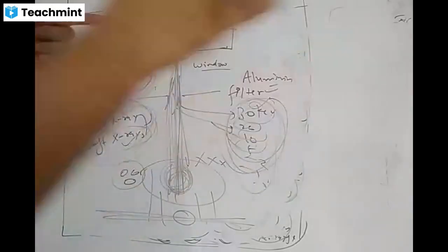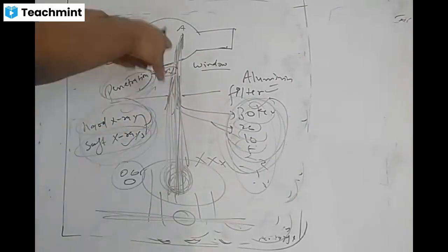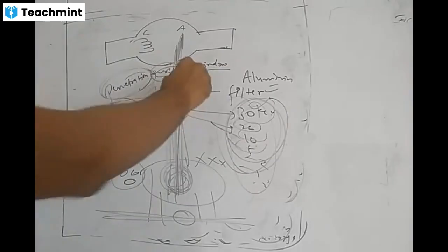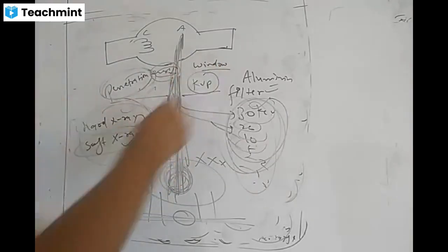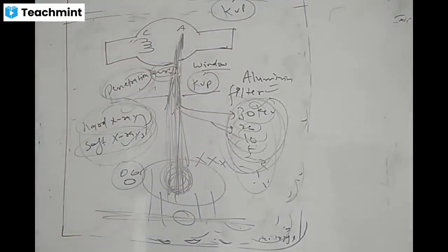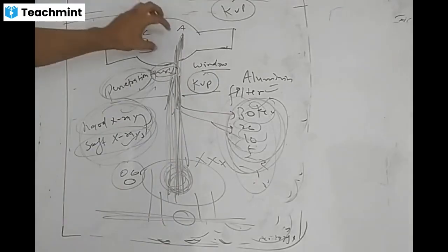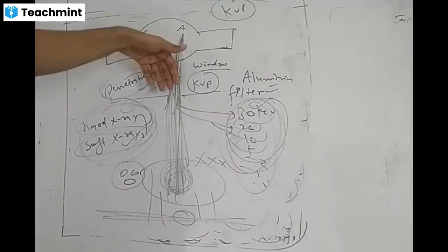Hard and soft is based on penetration, and penetration in turn is based on energy. The more energetic the X-rays, the more they penetrate. And how energetic they are is based on kVp. So the story ultimately starts at the kVp. The more the kVp, the more energetic the X-rays, and the more they penetrate.